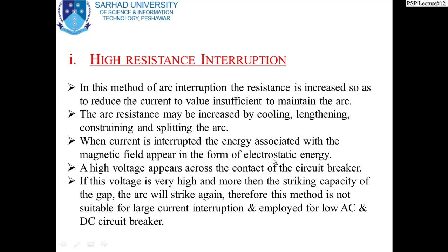Even when they are separated and there is an arc, the voltage is only 2 or 3% of the rated voltage. But when the arc is totally extinguished, the voltage rises to the system voltage, and this represents the electrostatic energy of the system. So the magnetic field energy or electromagnetic energy is converted into electrostatic energy. So from this sentence, it means like that, explained like this.